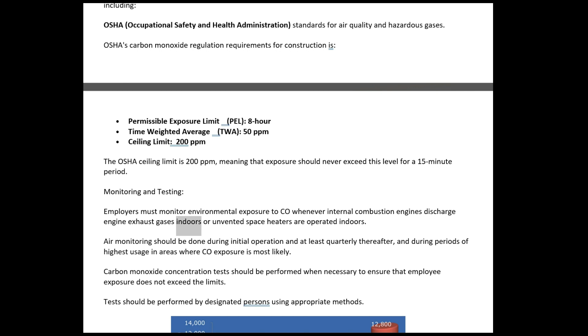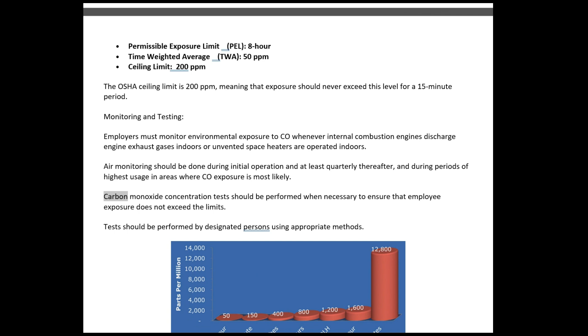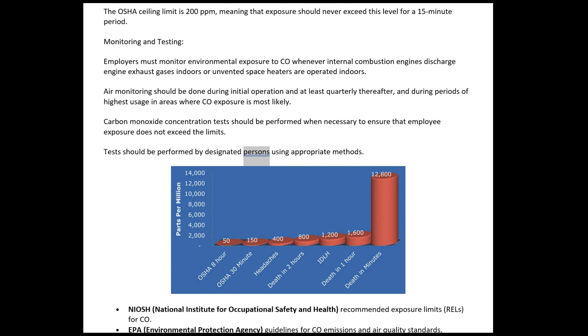Monitoring and testing. Employers must monitor environmental exposure to CO whenever internal combustion engines discharge engine exhaust gases indoors or unvented space heaters are operated indoors. Air monitoring should be done during initial operation and at least quarterly thereafter, and during periods of highest usage in areas where CO exposure is most likely. Carbon monoxide concentration tests should be performed when necessary to ensure that employee exposure does not exceed the limits. Tests should be performed by designated persons using appropriate methods.